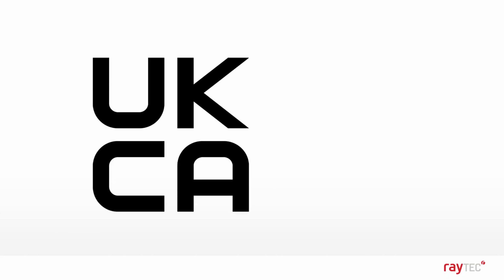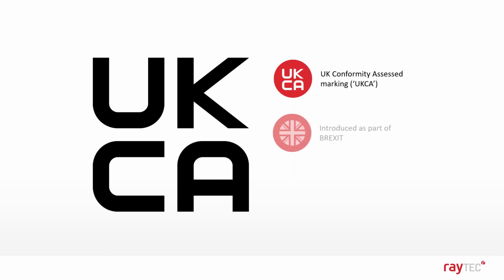So UKCA. Following the UK's departure from the European Union, we entered into a transition period which came to an end on the 31st of December 2020. From January the 1st, 2021, the UKCA mark, which is the UK Conformity Assessment, has replaced CE marking and declares that the product conforms to the applicable UK legislation to be placed on the market in England, Scotland and Wales. However, due to the Northern Ireland Protocol, goods in Northern Ireland will continue to require CE marking, or in some particular cases, UK NI mark.